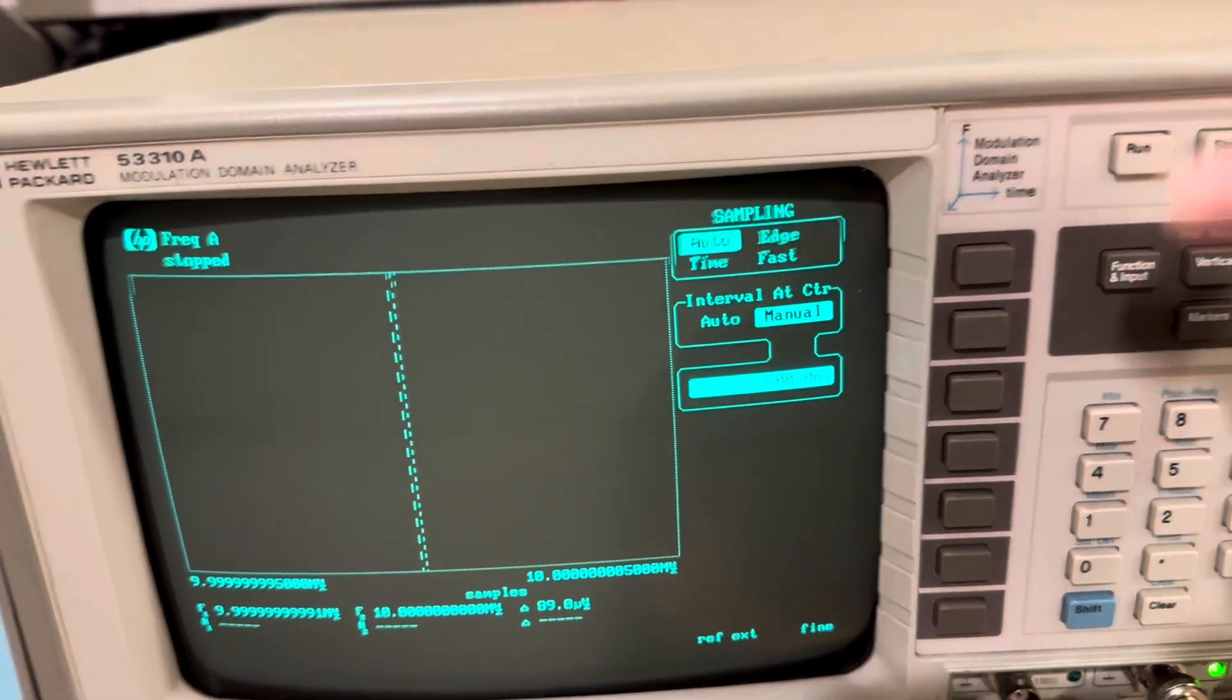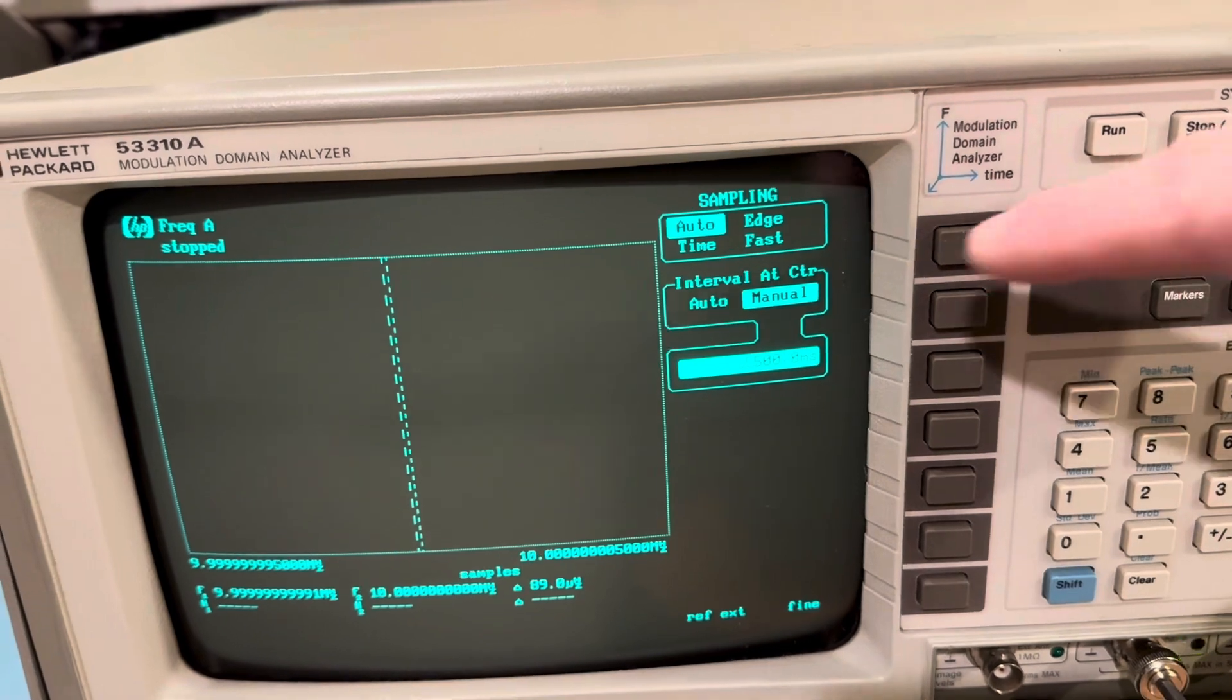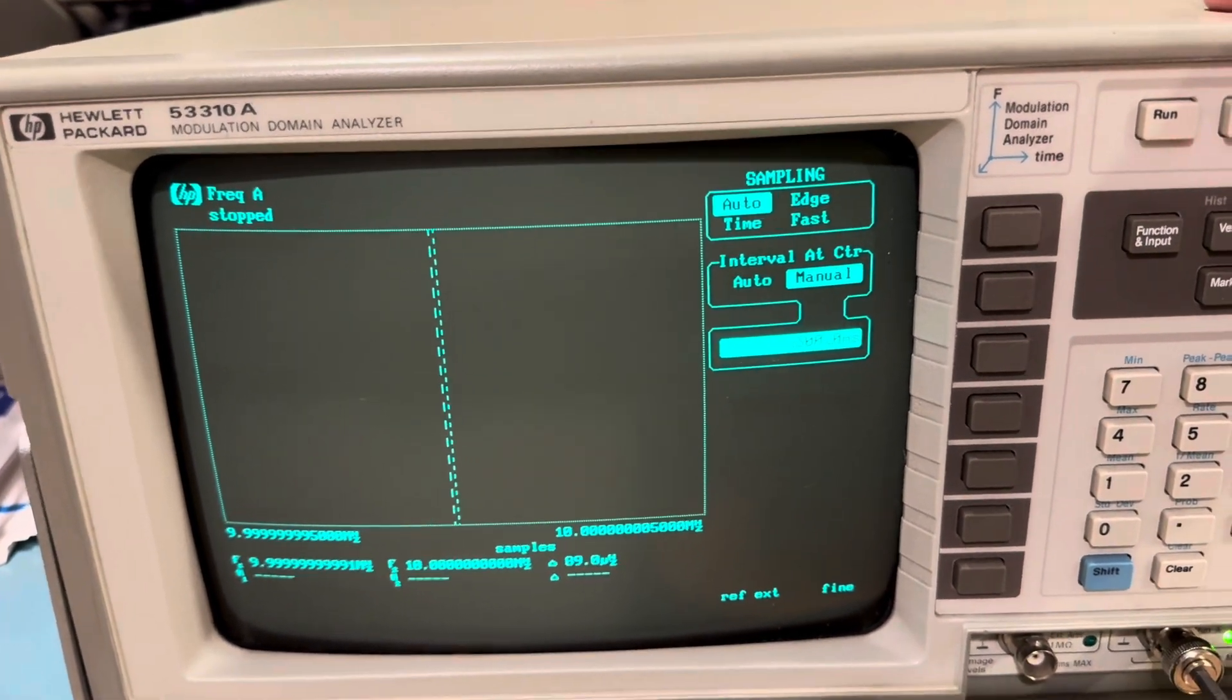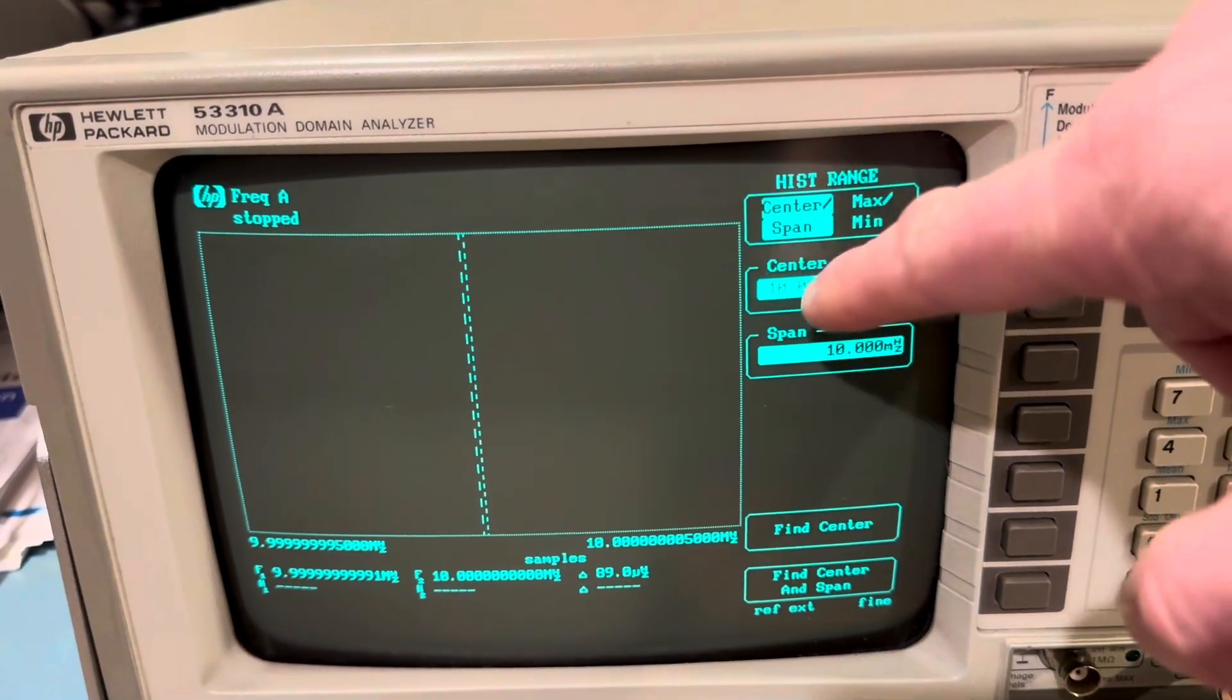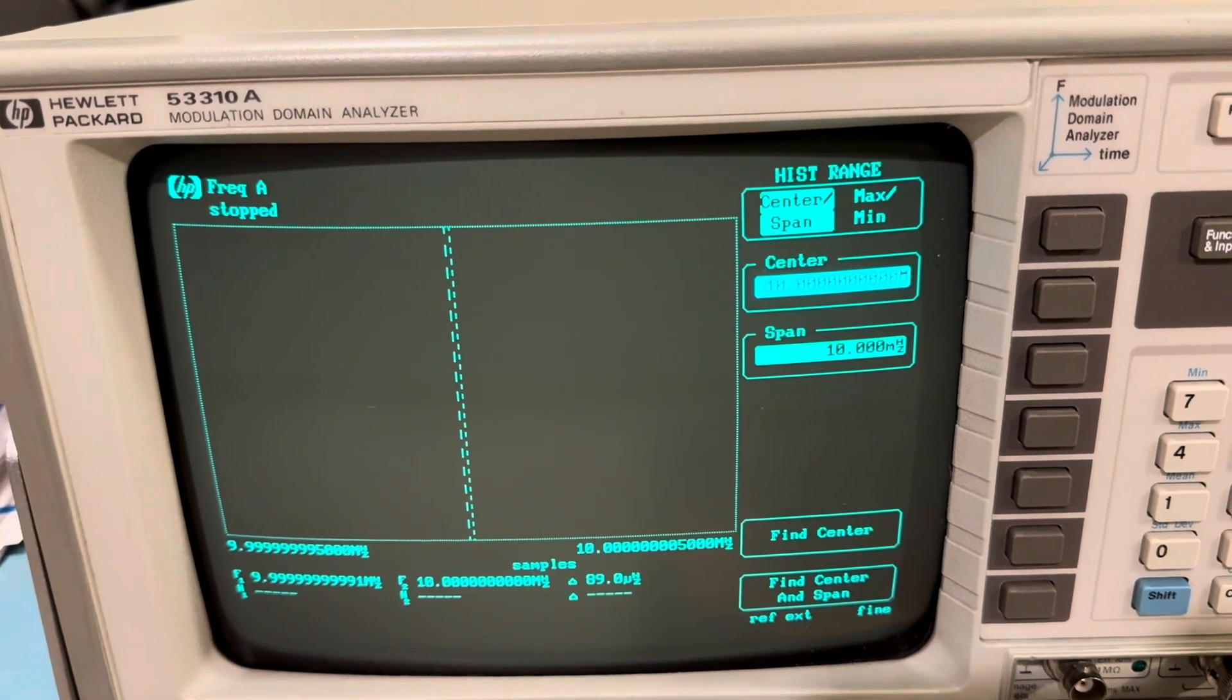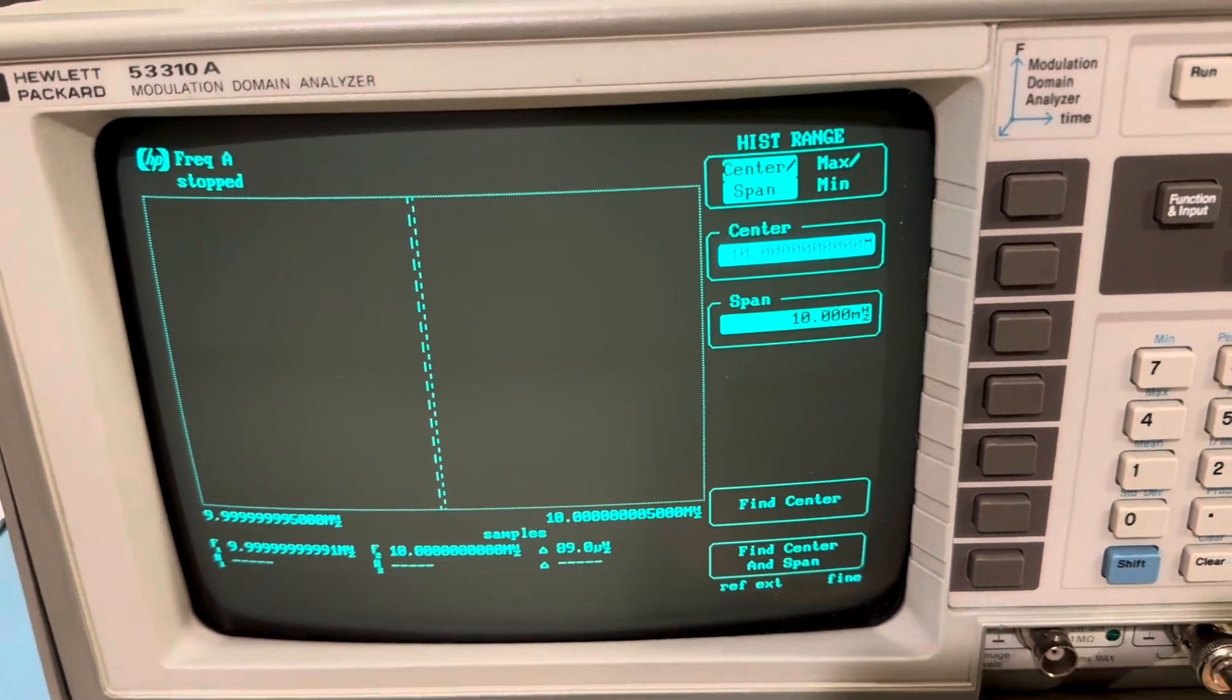And sampling is very important. I have it set for 500 milliseconds per sample. Manually set that. And sampling, we're going to set to auto. The vertical, I have it set to center of 10 megahertz exactly, a span of 10 millihertz. And I'll show you why I'm doing all this here in a second.